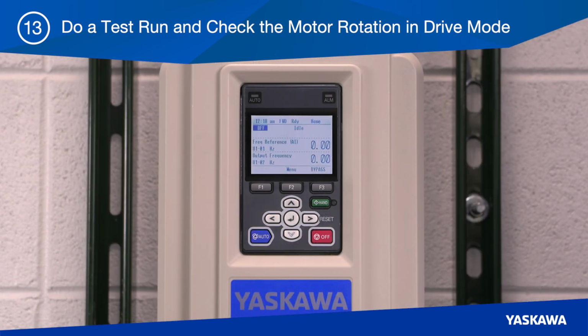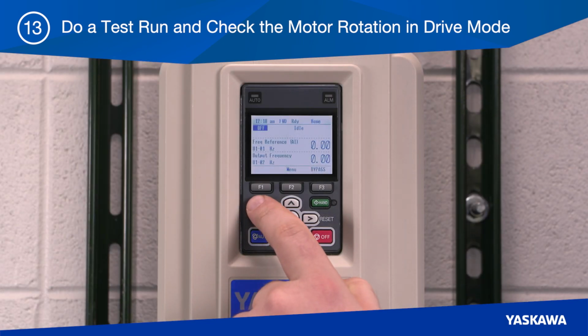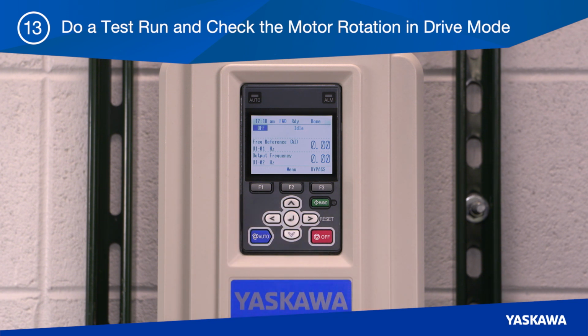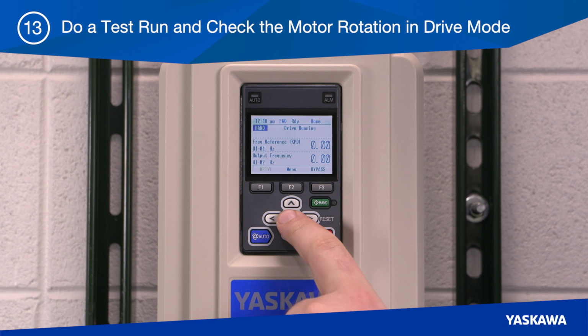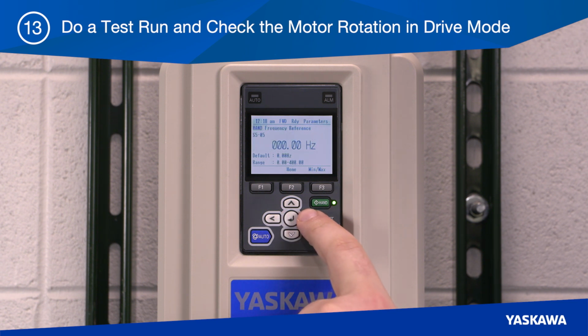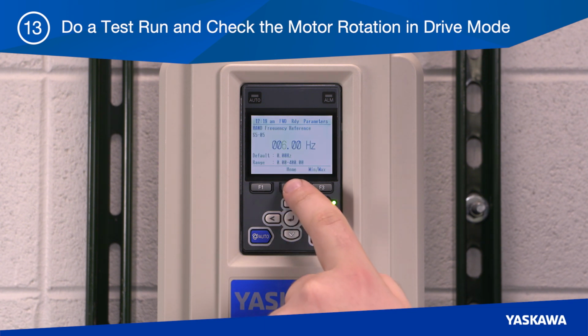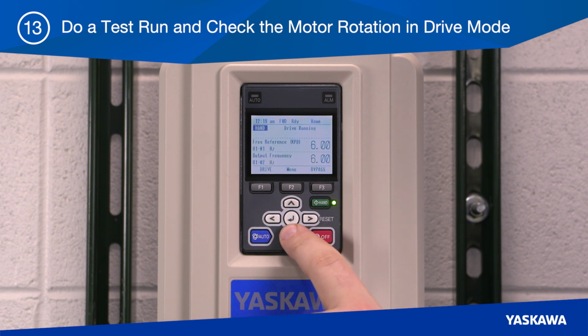Confirm that drive mode is selected by using button F1 on the keypad if needed. Then press the green hand button and press Enter. Set a hand frequency of 6 Hz and press Enter. Press the F2 home key. Then press the down arrow once.